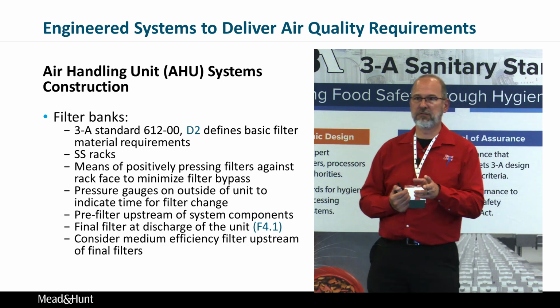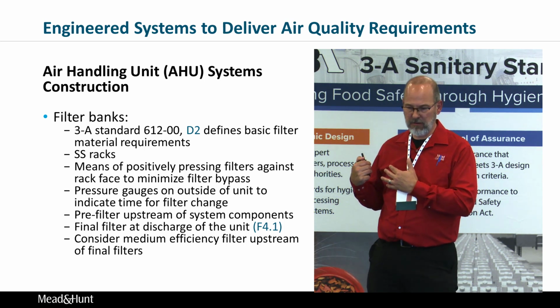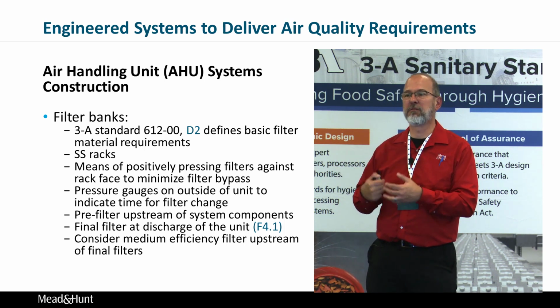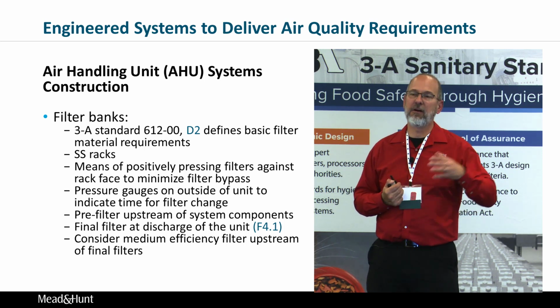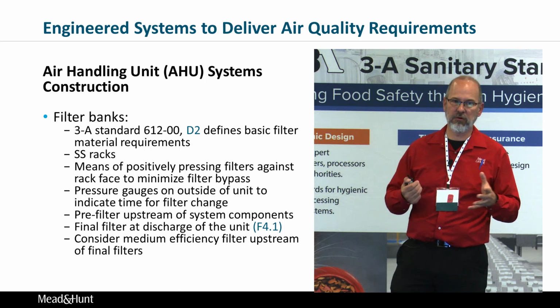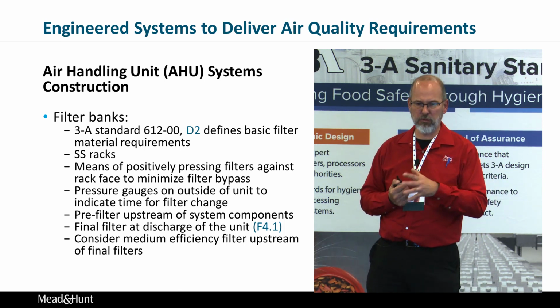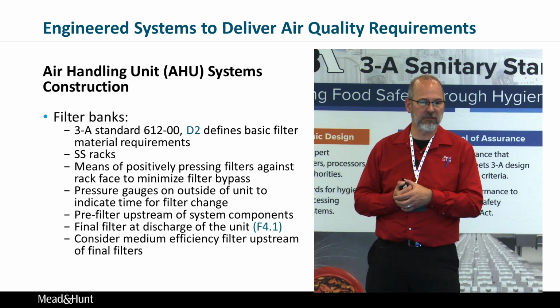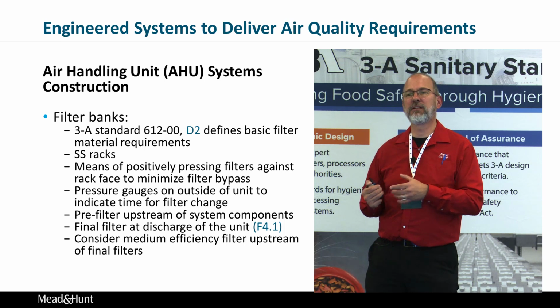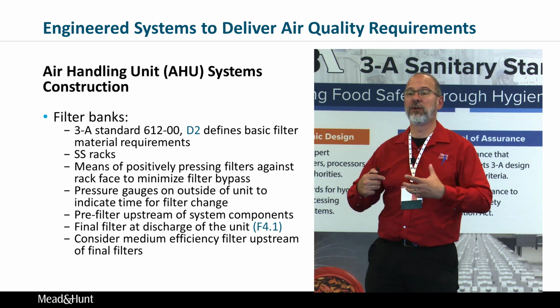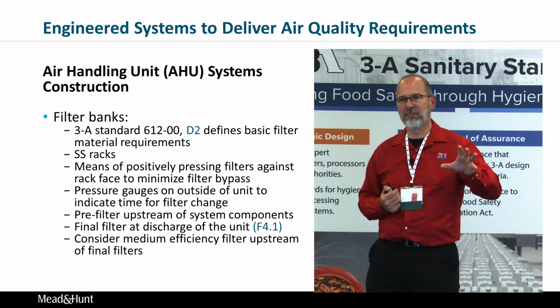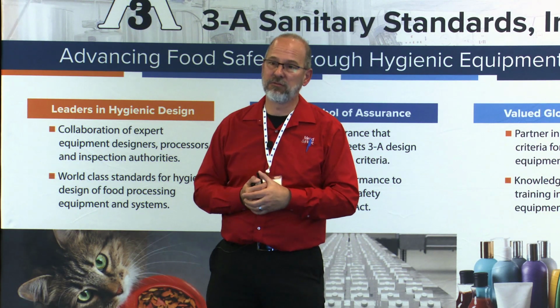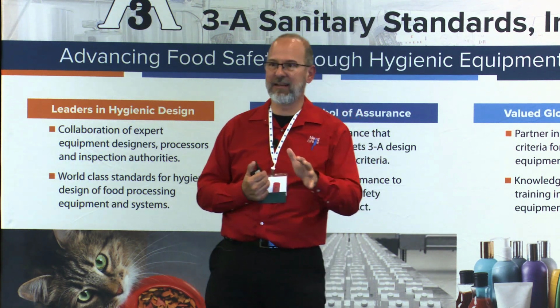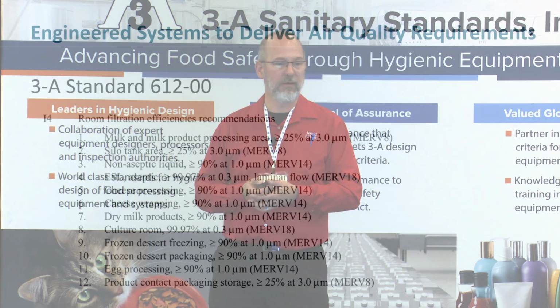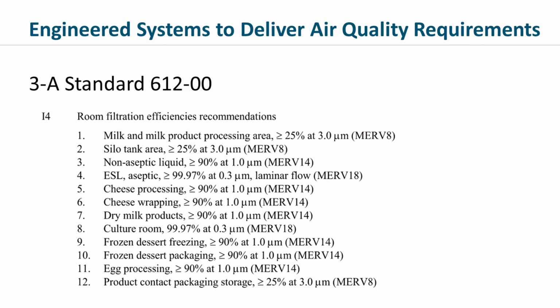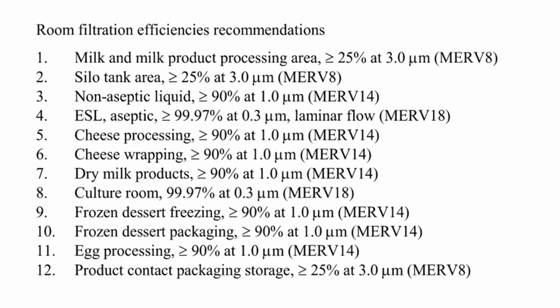Usually there's two sets of filters in a food grade air handler. There's pre-filters at the upstream side, to capture the big particulate that comes back into the unit from outside or the process space. And then at the very end of the unit, there's a final filter, which is typically a 12 or 24-inch deep filter. MERV 14 minimum typically, sometimes HEPA, MERV 18 filters, to catch any remaining particulate that entered the unit, as well as any particulate that could have been generated within the unit. So that final filter is the last element in the unit before the air leaves the unit and goes out to the process room. That's meant to catch anything that you don't want getting into the room. I'm not going to go into this in detail, but the standard 612 does have a list of typical MERV ratings for filters.